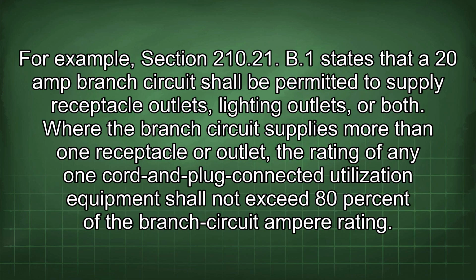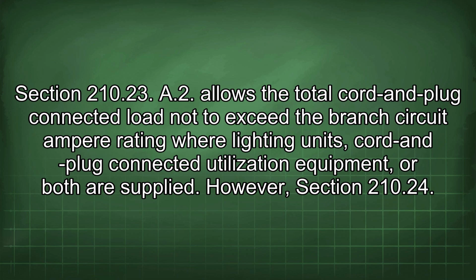For example, Section 210.21 B1 states that a 20 amp branch circuit shall be permitted to supply receptacle outlets, lighting outlets, or both. Where the branch circuit supplies more than one receptacle or outlet, the rating of any one cord and plug connected utilization equipment shall not exceed 80% of the branch circuit ampere rating. Section 210.23 A2 allows the total cord and plug connected load not to exceed the branch circuit ampere rating where lighting units, cord and plug connected utilization equipment, or both are supplied.